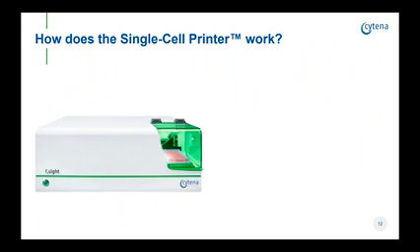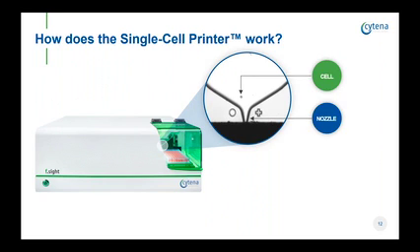Here you see the F.sight, our instrument for label-free and fluorescence-based isolation of mammalian cells. It's a benchtop instrument that is very easy to operate compared to other technologies such as flow cytometry. Zooming into the image here, you can see the nozzle of our disposable dispensing cartridge. We use an optical detection system, somewhat similar to a bright-field microscope, to detect cells in the nozzle. In addition, the F.sight comes with a laser and an additional camera that allows us to sort cells based on fluorescent markers.